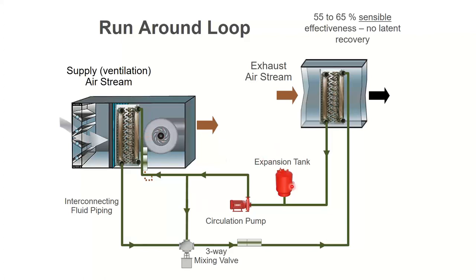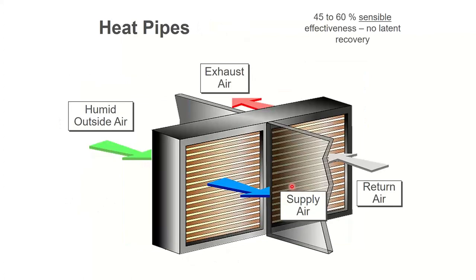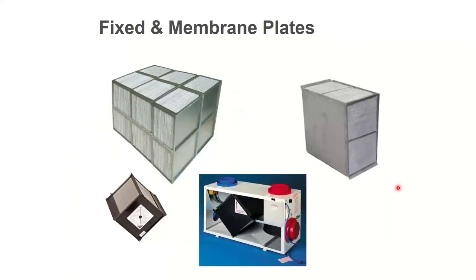And this works well when the exhaust air and supply air are far apart from each other, but you don't do any latent energy. Heat pipes also don't do any latent energy. They are essentially the exact same thing as these runaround coils, except instead of water, there's refrigerant in there. And the pipes have to be really close to each other. There's no compression cycle. It's just refrigerant in pipes. Each pipe is individual all on its own. Every one of these pipes has its own little refrigeration cycle, if you will, but no compressors on there. So I can't get to low temps, hence I can't dehumidify anything. But I can move BTUs from left to right or right to left. Sensible only, not good for code compliancy.